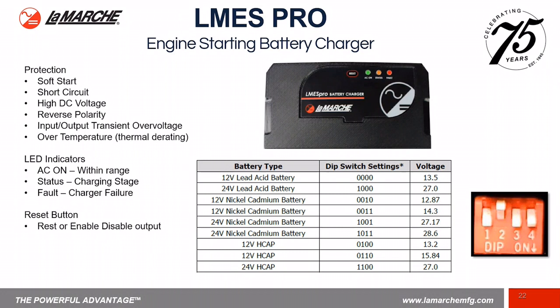It has 3 conveniently located LEDs right in front of the unit for AC on indication, charging status stage, and a fault indication if there's a charger fault. Here in the lower right hand corner is a setup of easily accessible dip switches where you configure the charger to charge lead acid, NiCad, or hybrid capacitor modules.